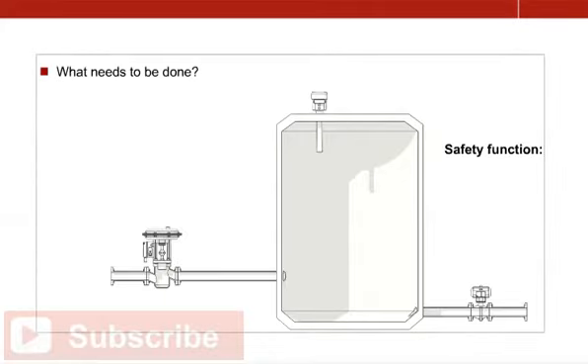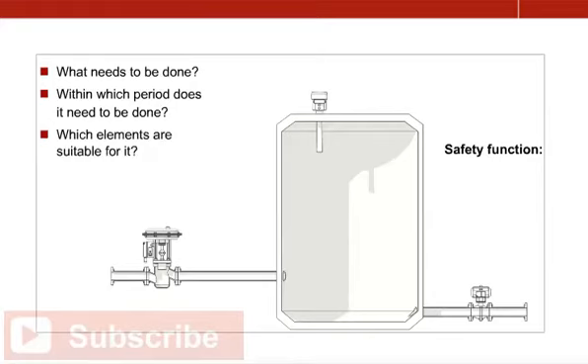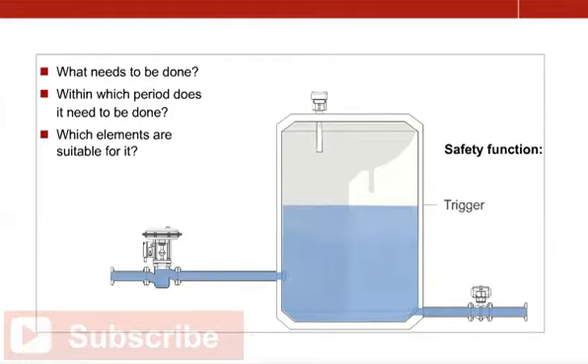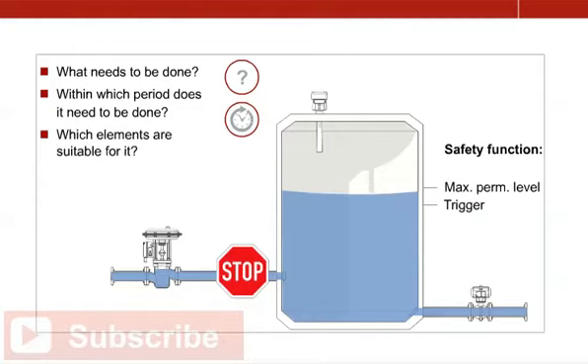Based on the hazard and risk assessment, it becomes necessary to install a safety function at a certain location in the plant. Such a function may involve shutting off the medium flow or draining the medium from a plant section. In addition to the function's effect, it's decisive that the function is completed within a certain period of time. Both criteria are crucial to device selection. When the outflow from the tank in our example is too small, the inflow must be shut off. This must be done so quickly that no impermissible filling level is reached. The required function can be implemented by using a control valve which shuts off sufficiently and closes quickly, in combination with a suitable level sensor and a control system to link them.